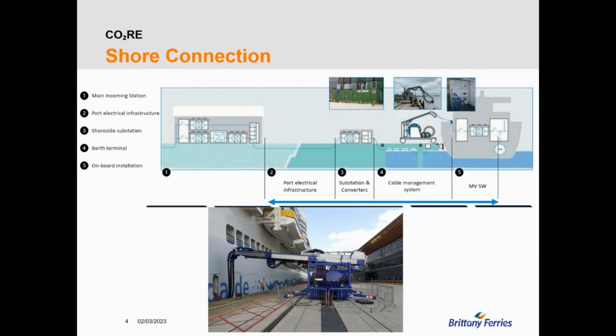The shore connection door is not located at the same place. We have a particularity on ferries, since we berth using ramps for vehicles. Longitudinally, we have to maintain the ship in a fixed position, which means the system bringing power to the vessel has to be able to bring the plug to the correct location, coping with longitudinal translation so the cable and plug can be brought just above the shore connection door.